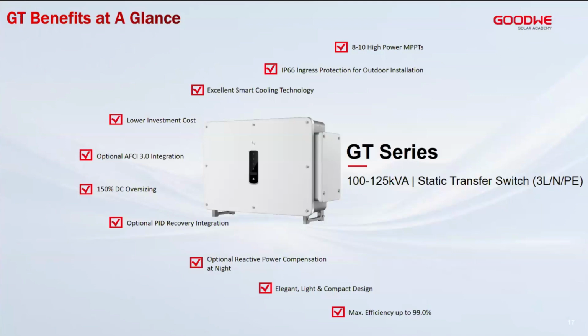With oversizing, the GT series can reach up to 150%, so it's quite flexible. The inverter also comes with PID recovery, that is, potential induced degradation for your PV panels. The inverter itself can repair that during the night. Reactive power compensation during the night is also an optional feature that you can integrate with this GT series. More features are integratable depending on your needs.